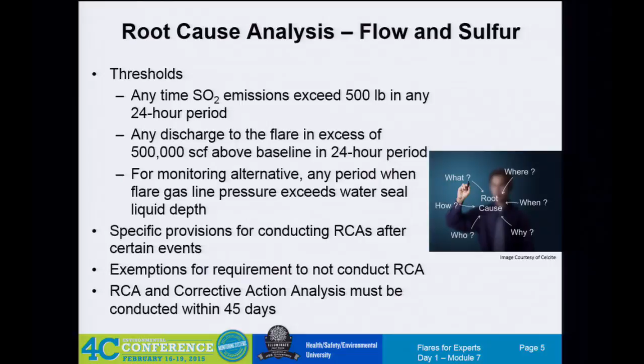So the flow meter, again, it was that simple thing of put in a flow meter. One of the biggest things is it must be maintainable online. They thought about the fact that if you need to go work on something, you have to pull something out of a flare header, and sometimes people don't like the flare to be operating when that happens. So they wanted to make it so if you had a flow meter there, you have to be able to retract those without shutting down the flare. They wrote that into the rule, and that has been able to be done. You're correcting for pressure and temperature, which is pretty much standard across all the flaring issues.